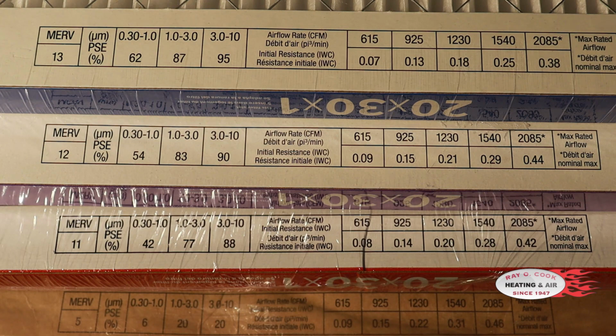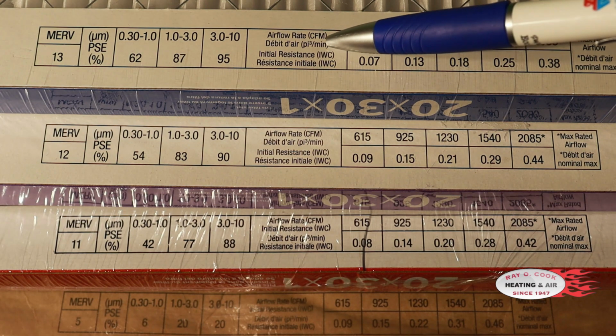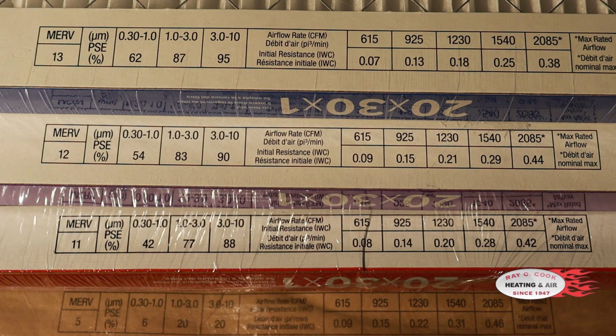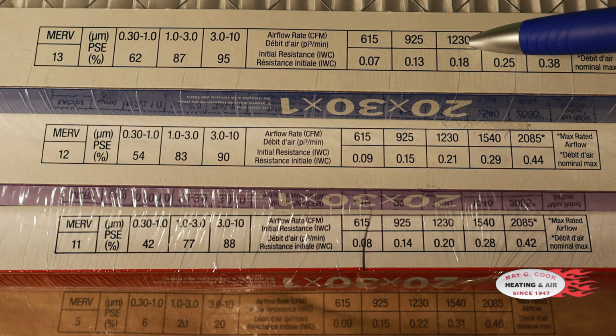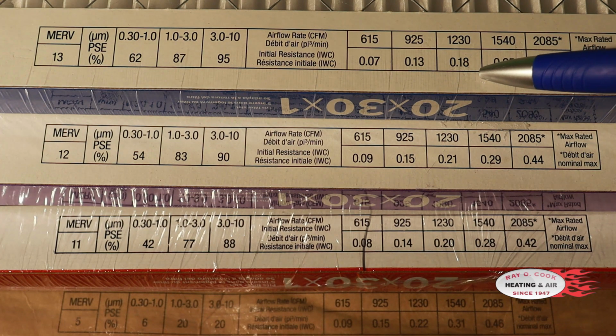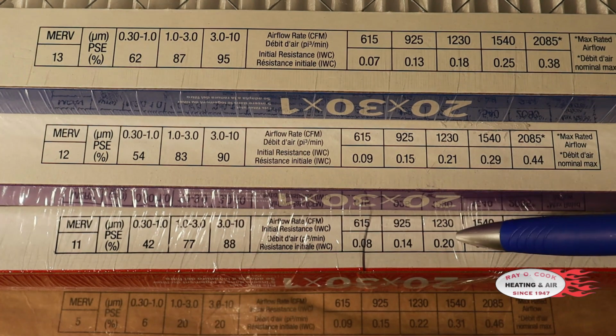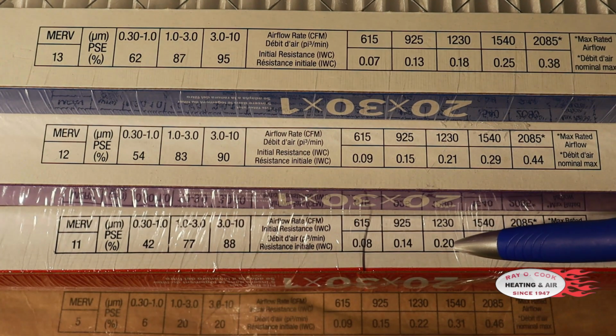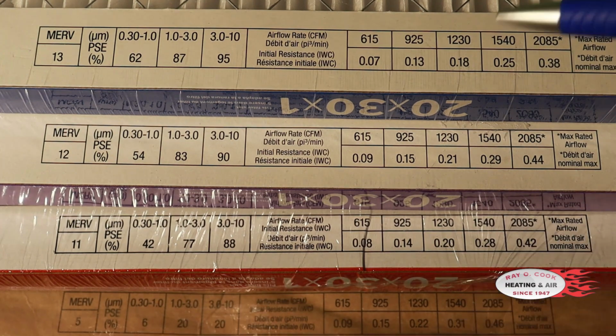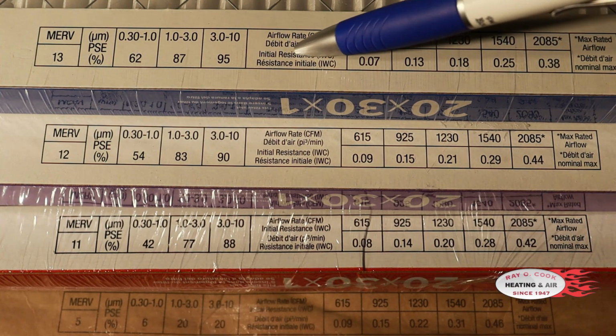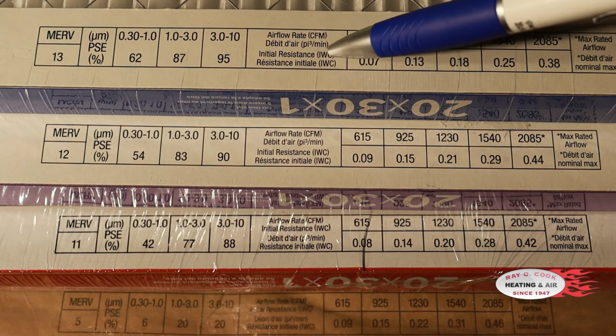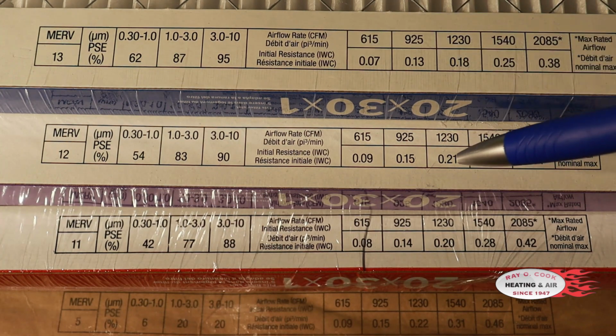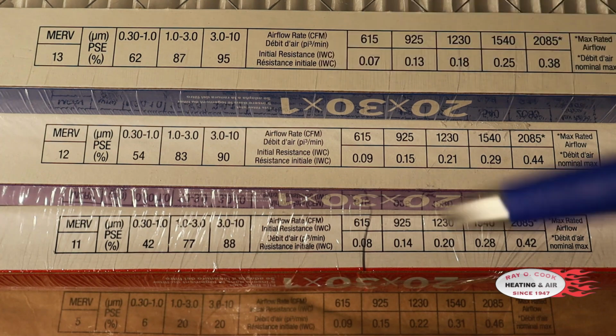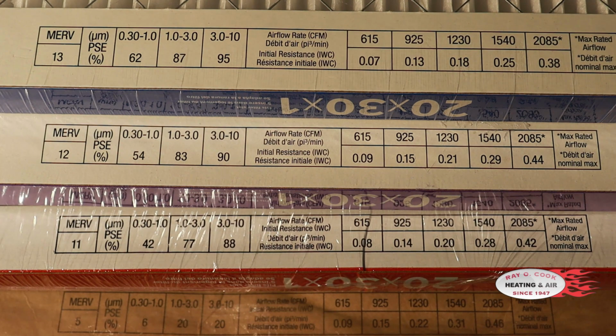But we need to pay special attention here to our CFM. So it says right here, airflow rate. CFM is going to be the volume of air. So that 1230 was our 3-ton offering, if we remember. We want 1200 CFM for a 3-ton unit. But look at our pressures. We're right at or over what we don't want to exceed at 0.20 on the pressure of our fan. So when we look at initial resistance, the resistance reading here, we don't want to be above this 0.2 rating ever. Initial resistance is meaning the filter is clean.